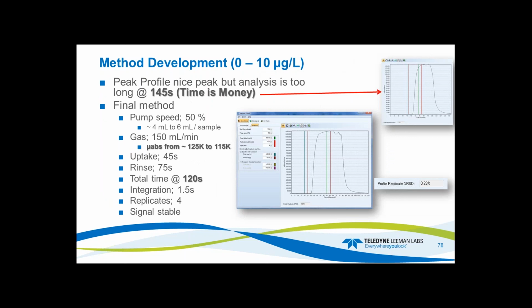And then I set the pump speed to 50, so that was the first time, 145 seconds. Gas, I've moved it up. Microabsorbance went from 125 to 115, no big deal. It's 125,000, no big deal. I changed my uptake to 45, rinse time to 75. Now I'm at 120 seconds.